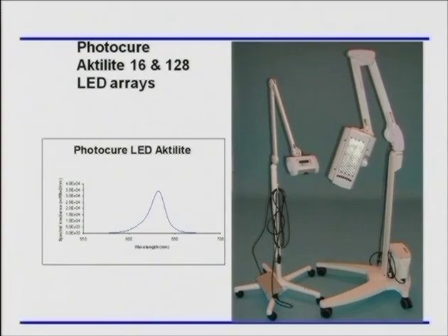You can work out some sort of standardized dosimetry so that you know from week to week or month to month how much light's coming out. And again, we don't do this every day. I think it's a 3-monthly measurement, which as things change slightly, we just alter our treatment times a little bit just to take account of the fact that the LEDs are deteriorating. But it's a simple enough thing to do.